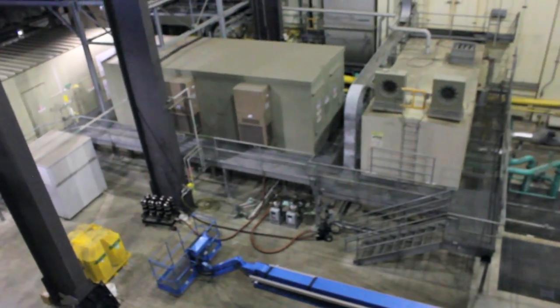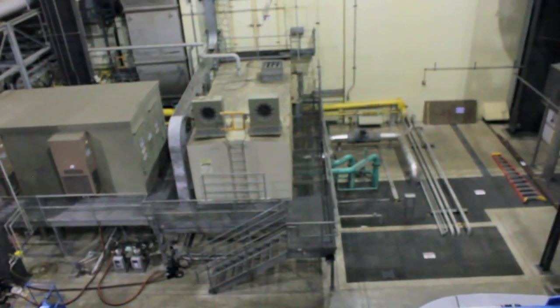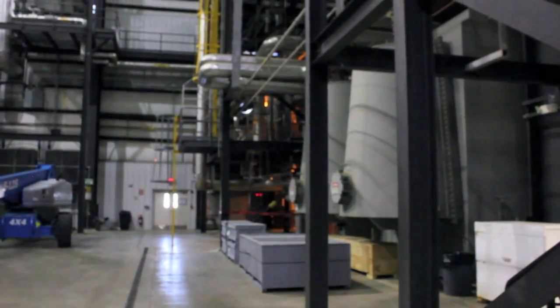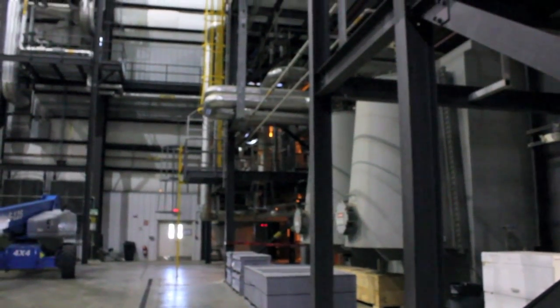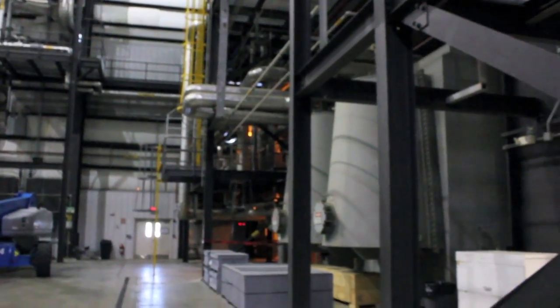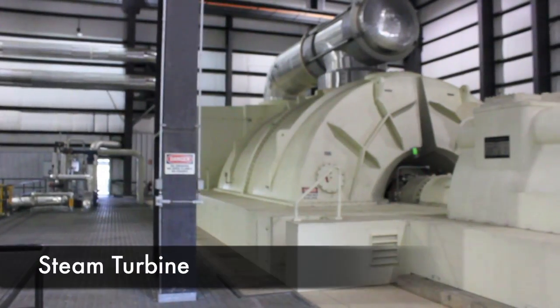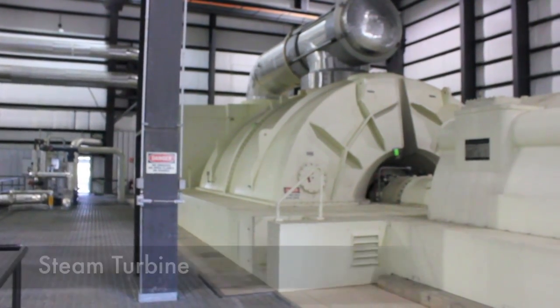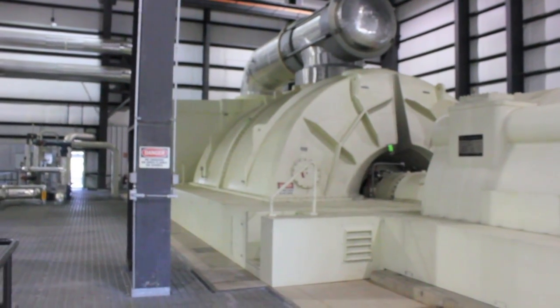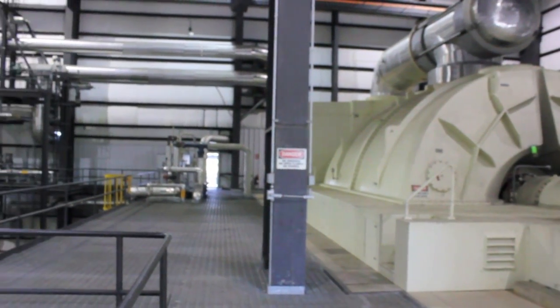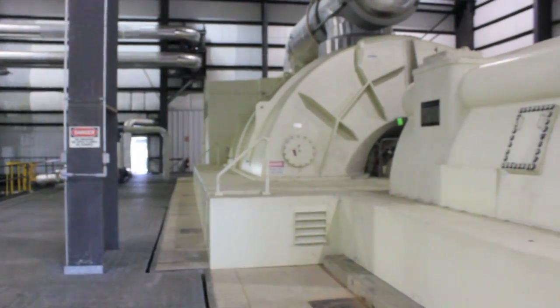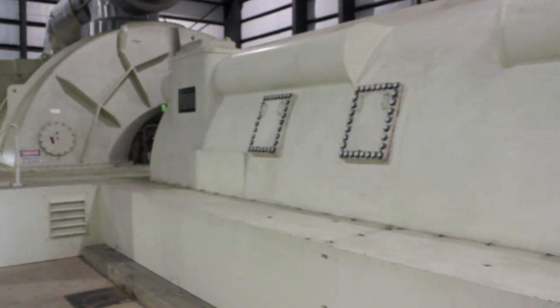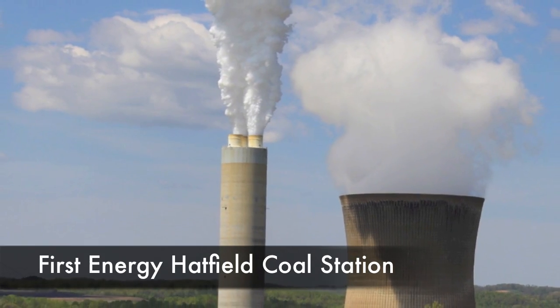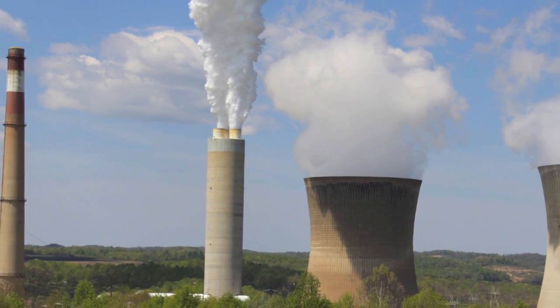We're going to go in the building now and we'll see the steam turbine and the condenser. The gray box you see here is the condenser. That's what takes the exhaust from the steam turbine that we'll see next and converts it back to water. Our steam turbine takes 3 different pressures of steam from the boilers. We have a high pressure, an intermediate, and a low pressure steam system. And those 3 pressures combined drive the steam turbine, which produces a little over 300 megawatts. If we were what's called a simple cycle plant, the exhaust of the gas turbine would go straight out the stack and would not have the efficiency that we have by driving a steam turbine.